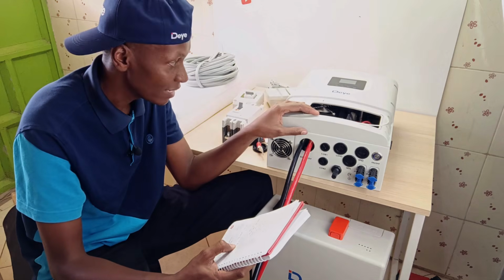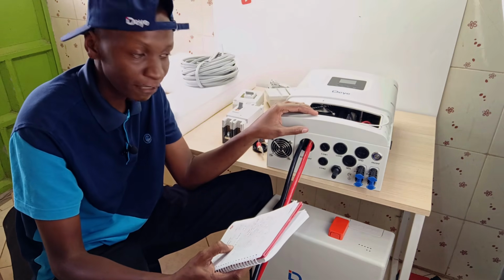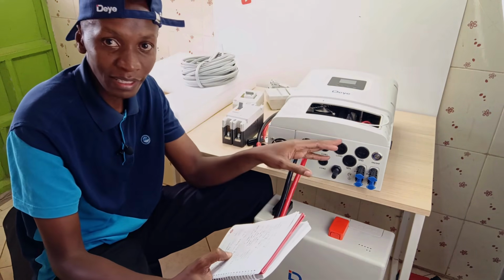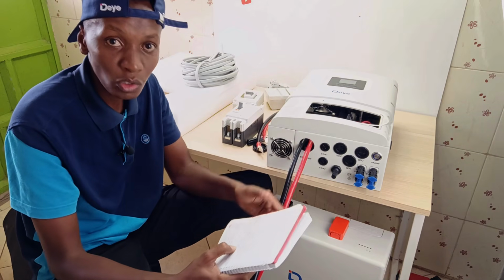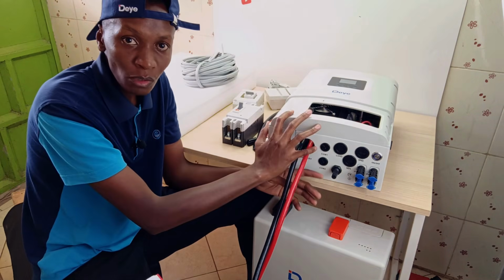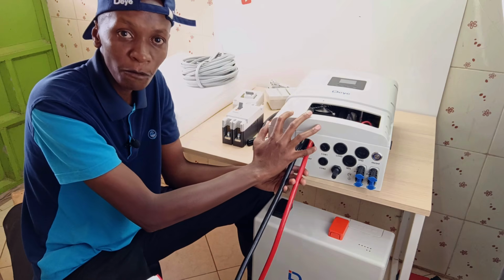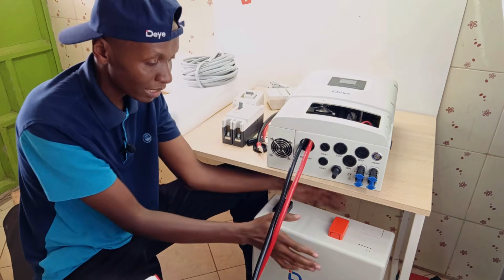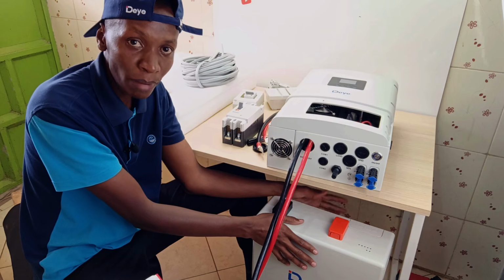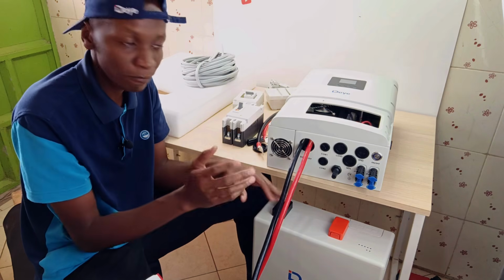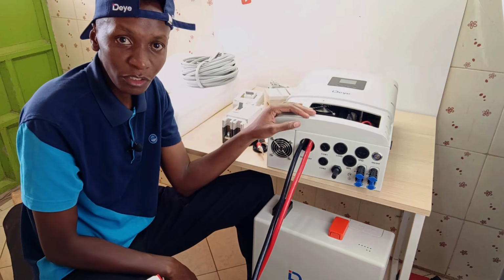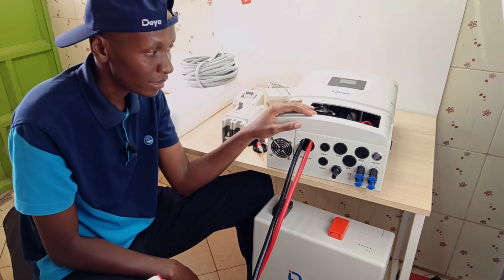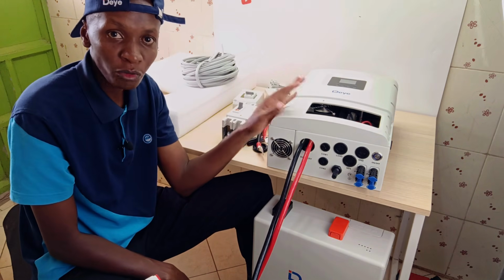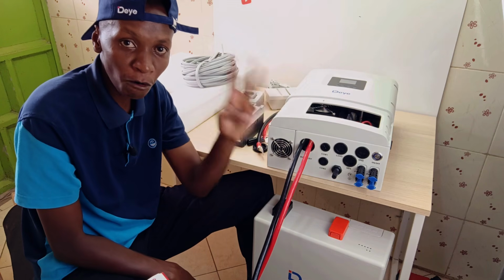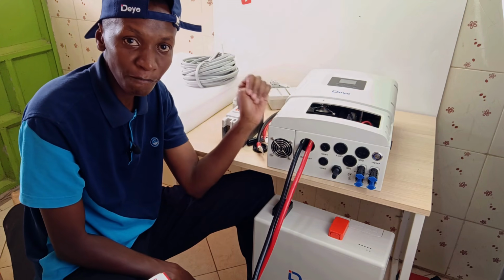Like I said, this is a 6 kilowatt hybrid inverter. It uses both solar and grid and can also be connected to a generator. The inverter works with a DC voltage range of between 40 to 60 volts. My battery pack here is a 51.2 volt battery pack, so it falls in between those voltage ranges. But you can also connect lead acid batteries to this inverter. If you have 12 volt batteries, you'll have to connect 4 of them so that you can get 48 volts.